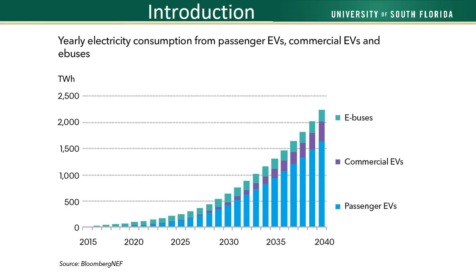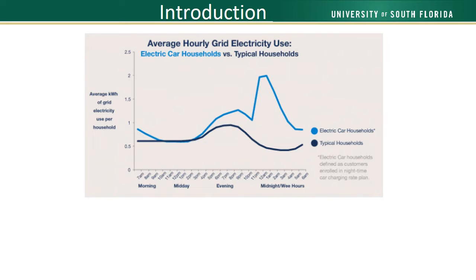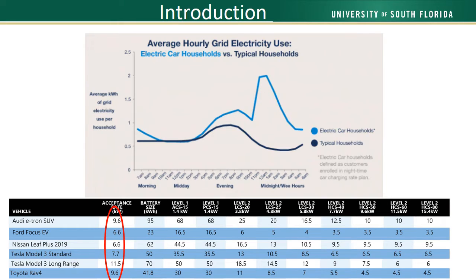Electric vehicles need to be plugged into an electric outlet rather than refueling at a gas station. Electricity demand from all kinds of EVs was 74 terawatt-hours in 2019, which will rise to 2,331 terawatt-hours in 2040. However, that will be only 6.8% of total global electricity in 2040. In fact, the impact of EV inclusion is more significant in peak power demand than in total energy consumption. The graph shows the average peak demand of a household with electric cars is more than double that of a typical household. The existing residential distribution grid is not designed to account for EV loads. A regular home in the US has an average load of 1.2 kilowatts. At the same time, an electric car, such as the best-selling Tesla Model 3, adds another 7.7 kilowatts of load to the household, effectively more than doubling the peak electric demand of the home.